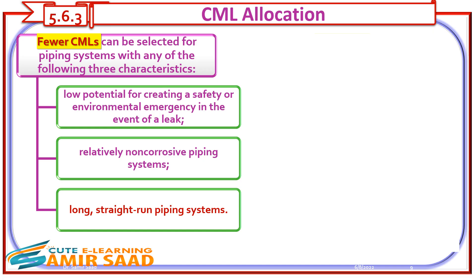Circuits with corrosion environments which have experienced unexpected failures in the facility or elsewhere in the industry also require more CMLs. Fewer CMLs can be selected for piping systems with any of the following characteristics: low potential for creating a safety or environmental emergency in the event of a leak; relatively non-corrosive piping systems; and long, straight-run piping systems.